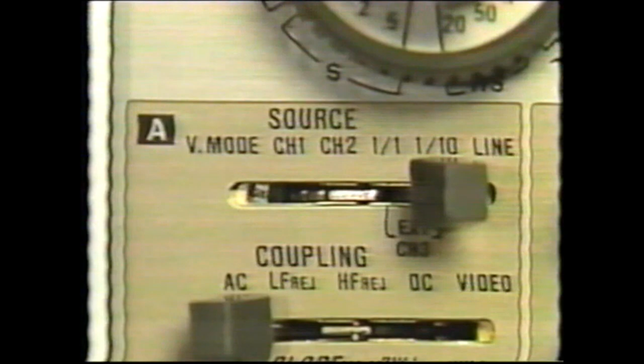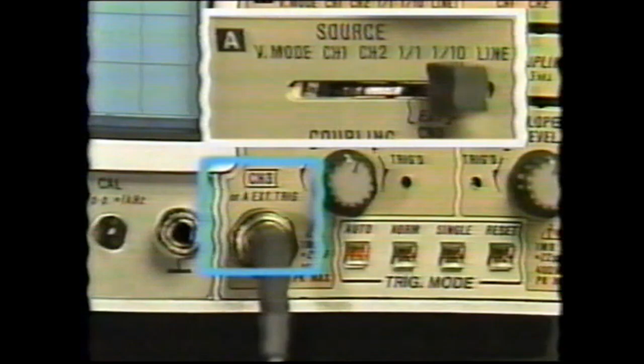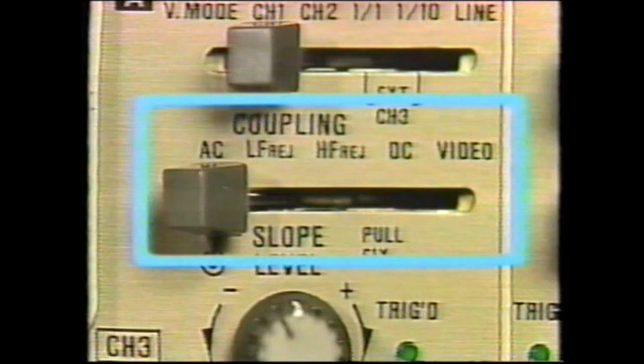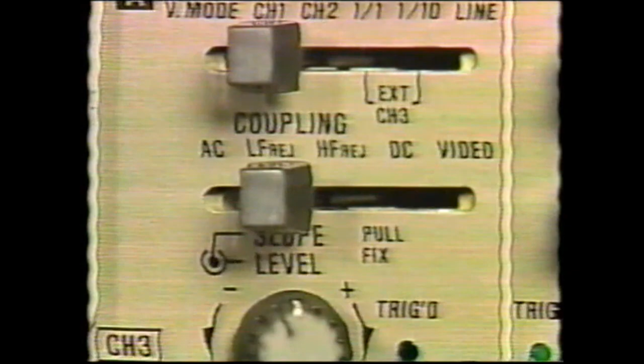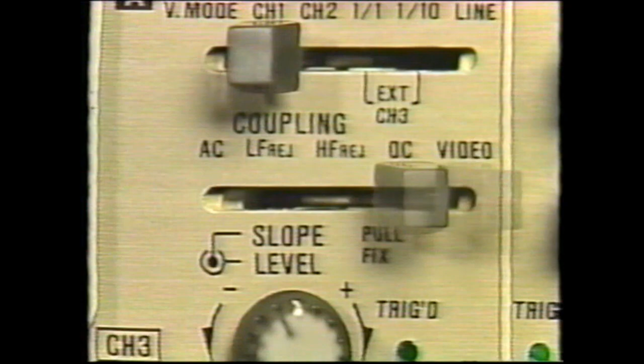In the 1:1 or 1:10 external channel 3 position, the signal applied to the A external channel 3 jack becomes the trigger source. The trigger coupling control has 5 positions. They include AC, low frequency, high frequency, DC, and video. In the AC position, all DC or direct current in the trigger signal is eliminated. This position is recommended for viewing most waveforms.